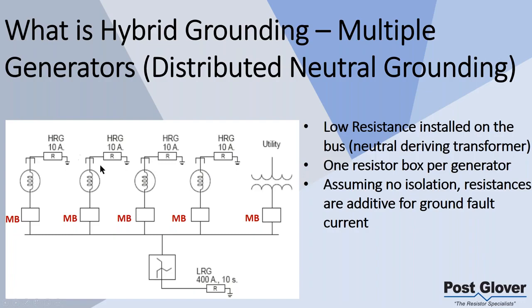Because of all the available ground fault points, your total overall current is 440 amps. So you'd be acting as a low resistance ground system with 440 amps for almost all scenarios, except for faults internal to the generator, where you would figure this out based off of the relaying that we'll talk about in a second, and you would trip your breaker here.